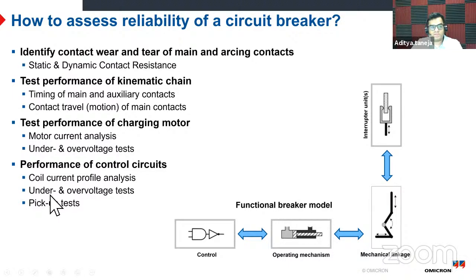There is an under voltage test and over voltage test to make sure that these coils work in boundary condition, not only in the nominal condition. Because if there is any chance of failure, it will first start showing in the boundary conditions. That is the upper limit of the coil operation and the lower limit of the coil operation. And also there are some minimum pickup tests to know what is the force needed for the coil to operate, because that force is proportional to the overall health of the coil.